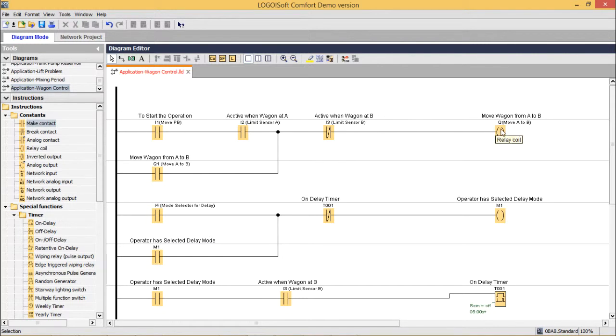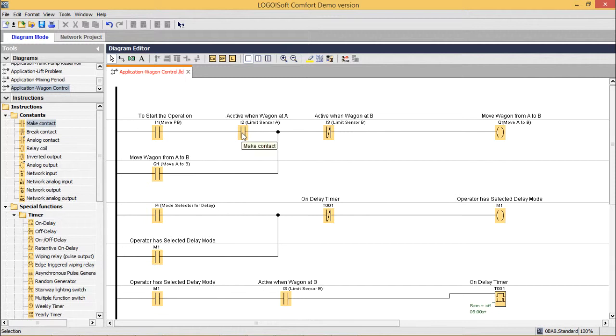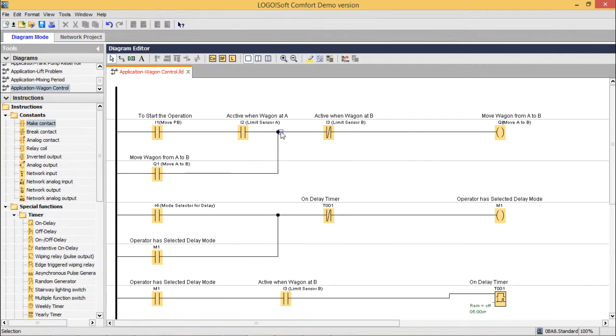To make Q1 on (wagon moves from A to B): when the start push button is pressed and the wagon is at limit sensor A, Q1 activates. Since it is a push button it will go off when released, and once the wagon leaves sensor A, sensor A can no longer detect it. So a parallel latch is provided: once Q1 is on it remains on until limit sensor B detects the wagon has arrived.